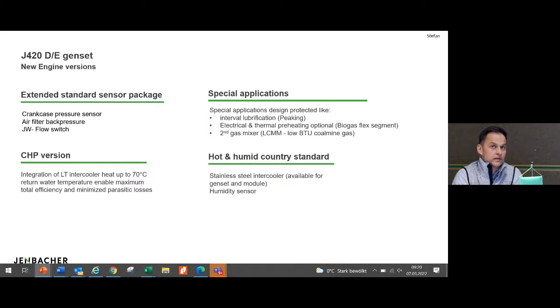As Steve said, with the new DE concept we are able to keep the same proven fuel flexibility we had on the current design or on the B and C. So with special tools or with a second gas mixer, we are able to run on low coal mine methane gases or low BTU coal mine gases. We have the electrical and thermal preheating option, and a peaking application designed with the interval lubrication function. For hot and humid countries, a stainless steel intercooler is now available for the module and the genset. For both applications, a stainless steel intercooler is available, and we have implemented the humidity sensor there.